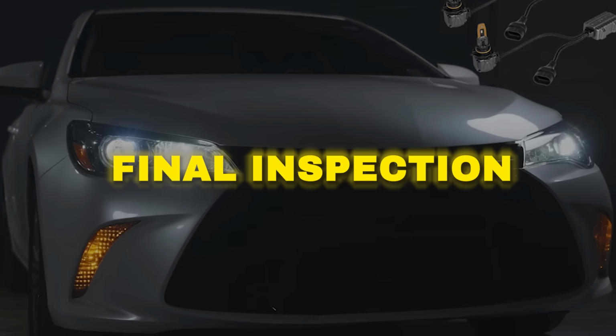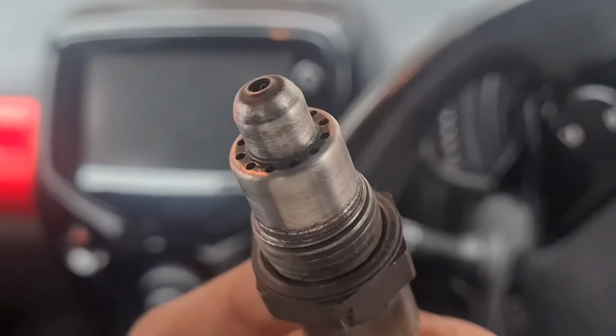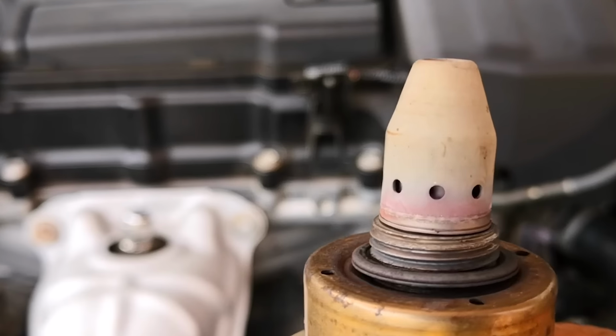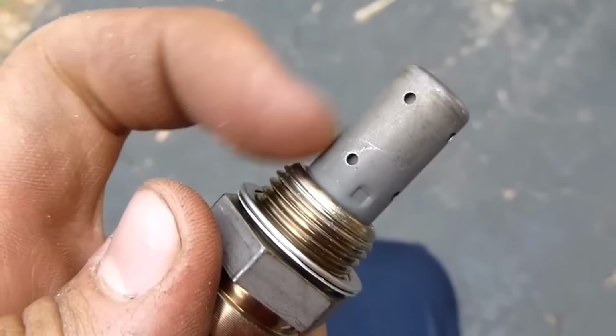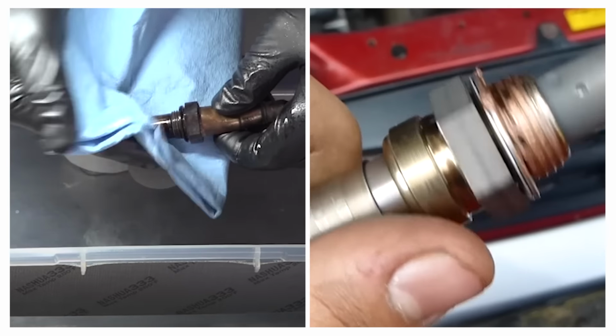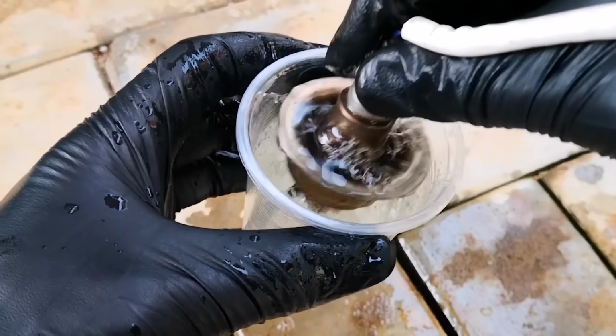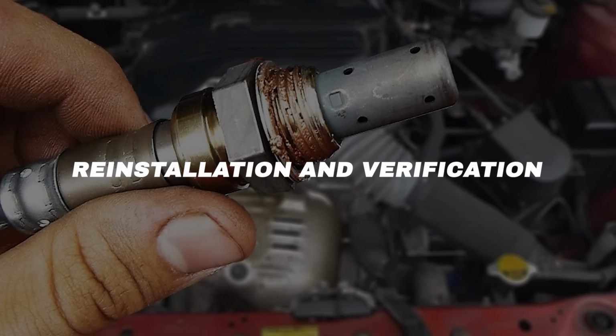Step 10. Final inspection. Under bright light, inspect the sensing element. It should look grayish-white or light tan, not black, not shiny with any coating. If it's still heavily black or has a shiny coating, the sensor is contaminated beyond cleaning. Replacement is necessary.